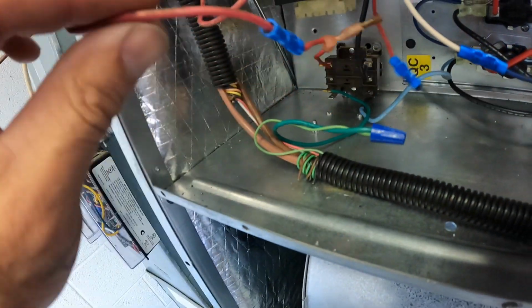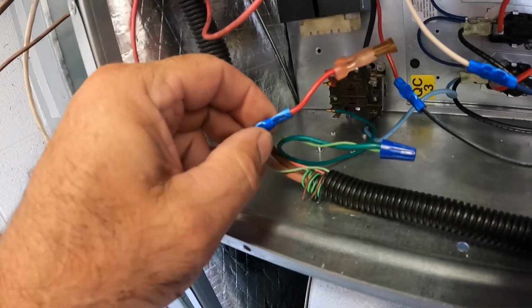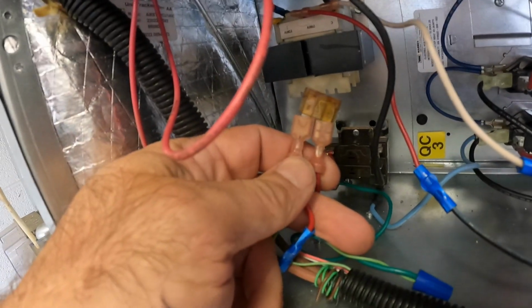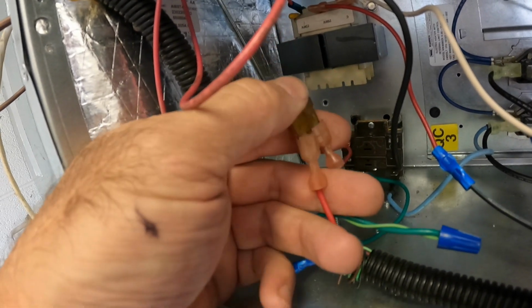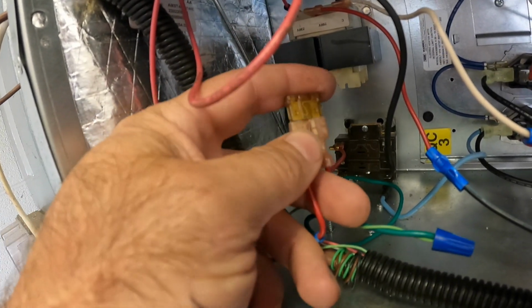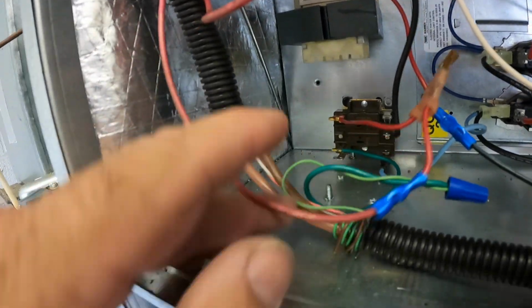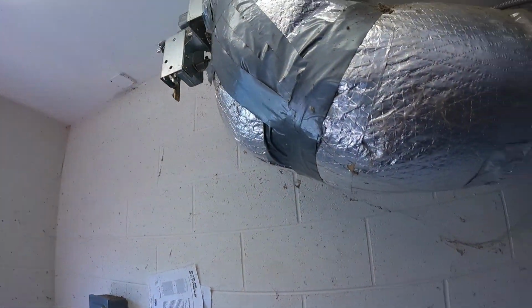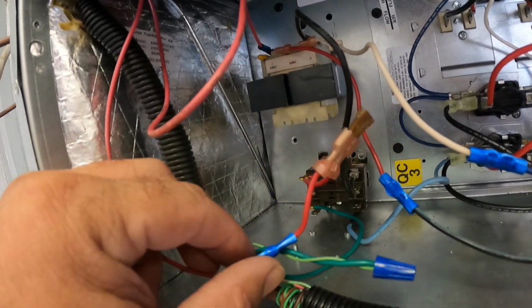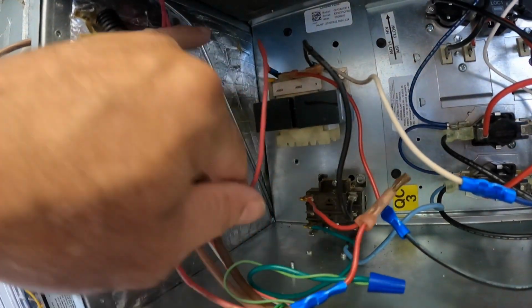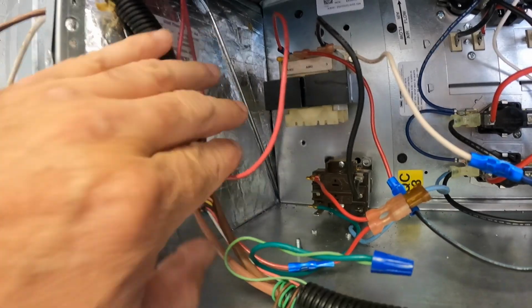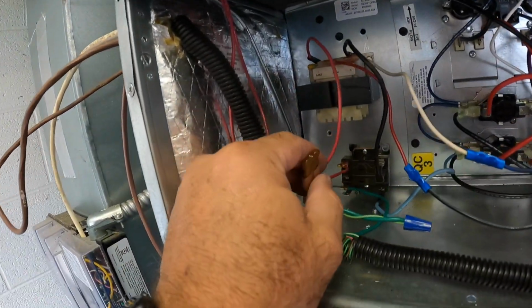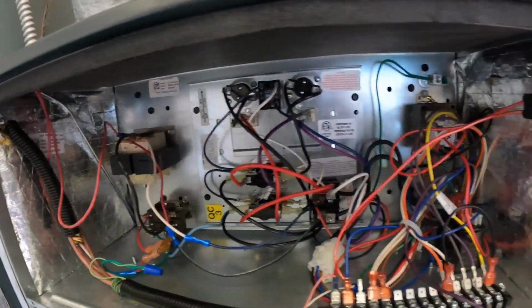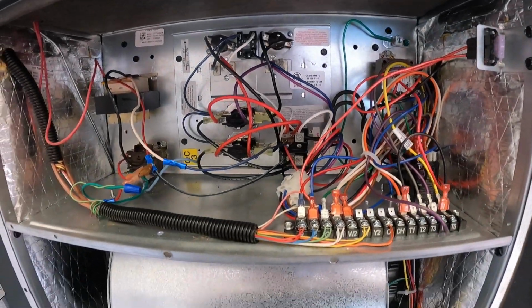So I ran it over to the normally open side, and then I took the other wire going up to the damper and repurposed the fuse holder out of the old air handler, which is nothing more than a fuse and a couple of connectors, and put a fuse on that in case that motor ever has an issue. It can pop that fuse instead of that transformer. So I'll end up tidying that up a little bit, maybe tying everything over here out of the way, but all in all, it's pretty clean in there for everything that's going on.